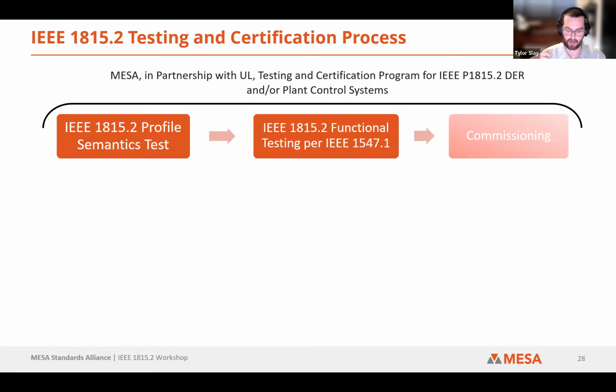And then you get to the final stage, which is commissioning. This is where you're in the field - most likely a large plant, a large control system where you can't bring it into a lab to have it tested. So you go out to the field. You're working with a lot of different utilities, working with interconnection agreements defined by balancing areas. So it's a lot more complex of a task.